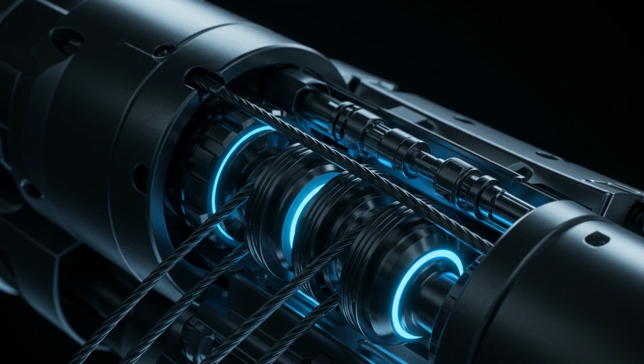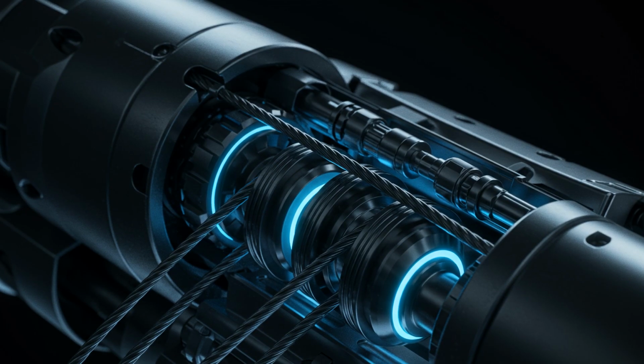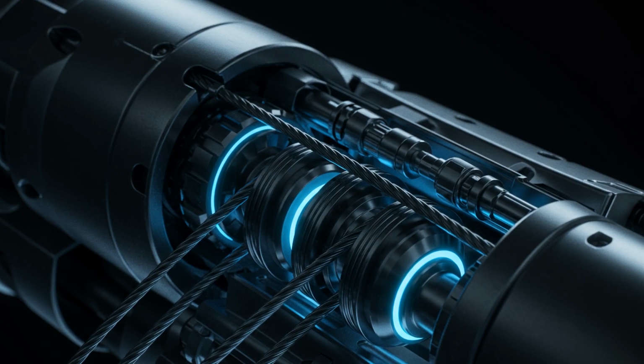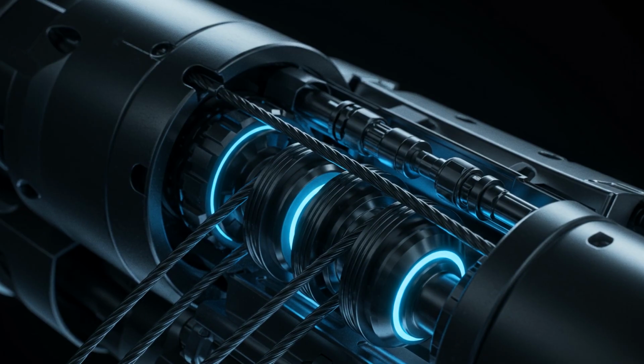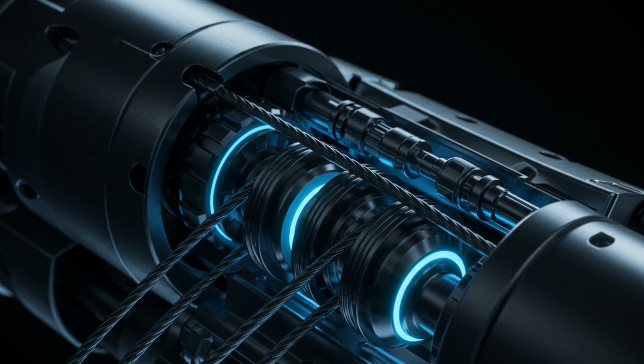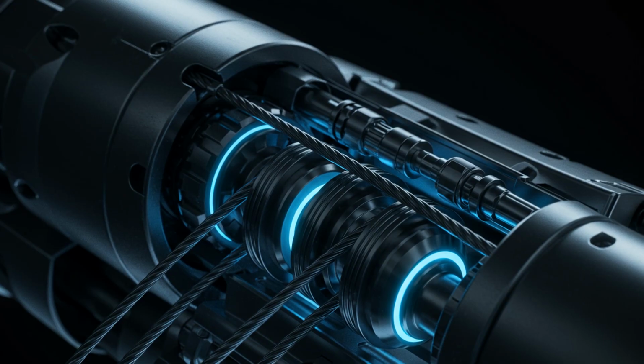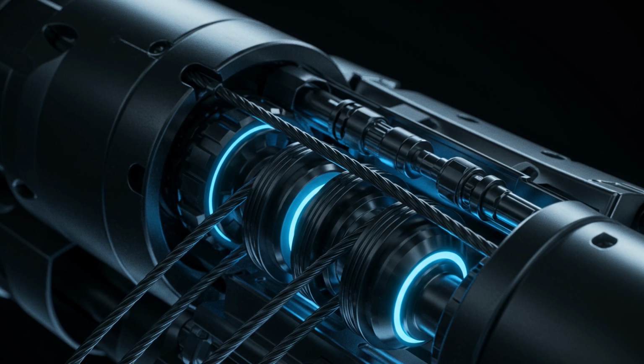Deep inside the robotic arms, movement is transmitted not by heavy shafts, but by a network of high-strength cables, the tendons of the machine. These are often made from tungsten or proprietary stainless steel alloys, woven into ultra-thin strands for maximum flexibility and zero stretch. Each cable must withstand hundreds of pounds of tension without elongating even a fraction of a percent. They are routed through a series of micro-pulleys and fairleads designed to minimize friction. If a cable were to stretch or fray, the robot would lose its micron-level accuracy.